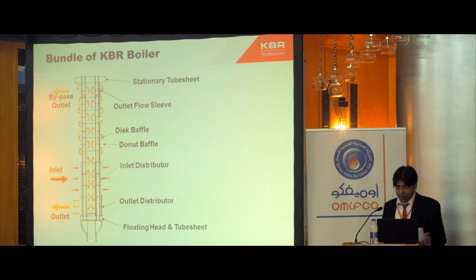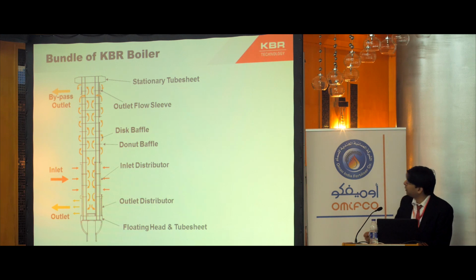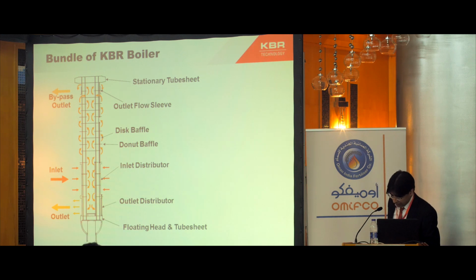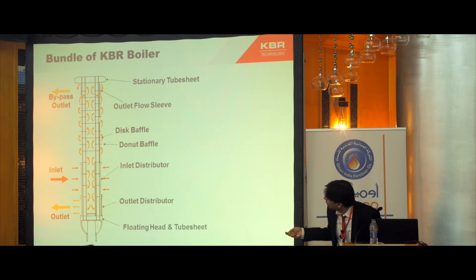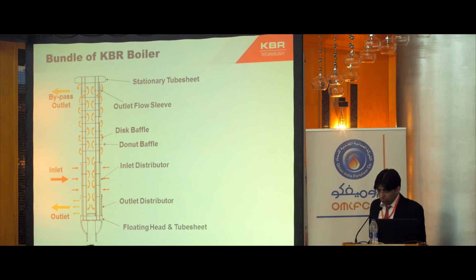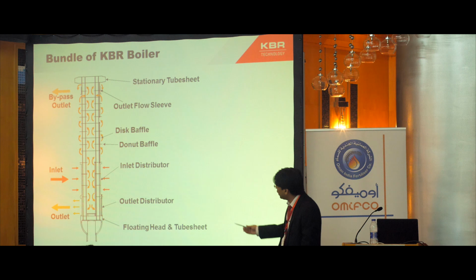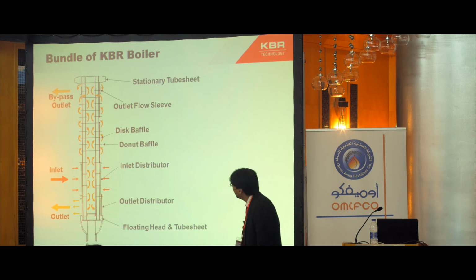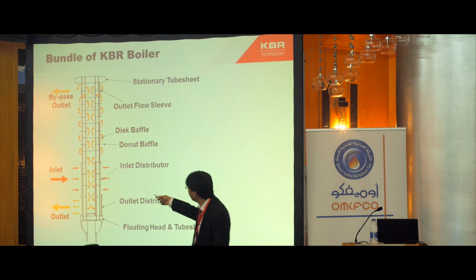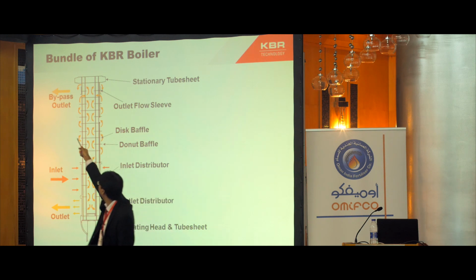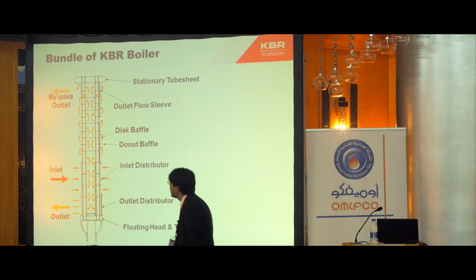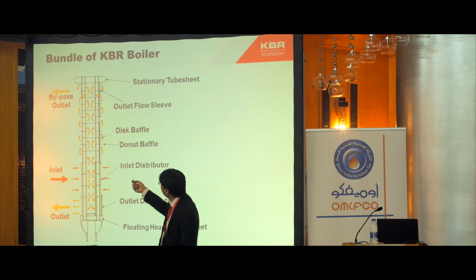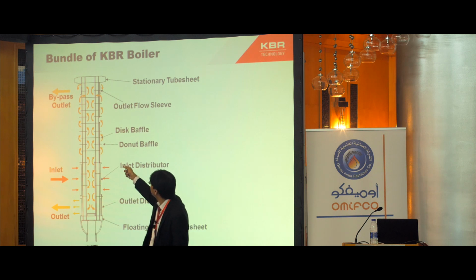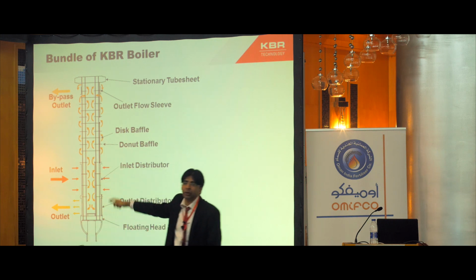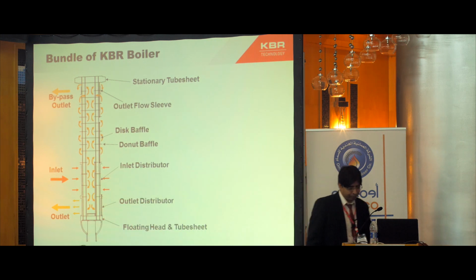The flow of the process gas side is radial, with a disc and donut baffle design. So the flow is split unequally between the outlet distributor and the bypass outlet. There are two outlets, one is this one and the second is the bypass outlet. There are disc and donut baffles which basically guide the flow over to the shell side of this waste heat boiler.